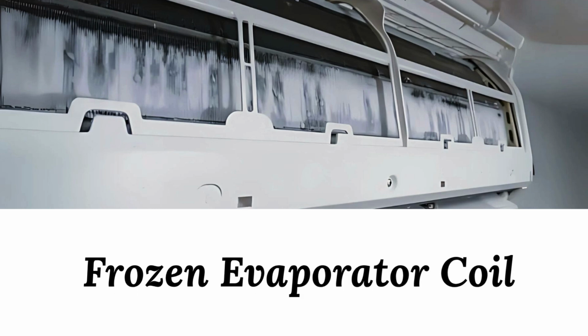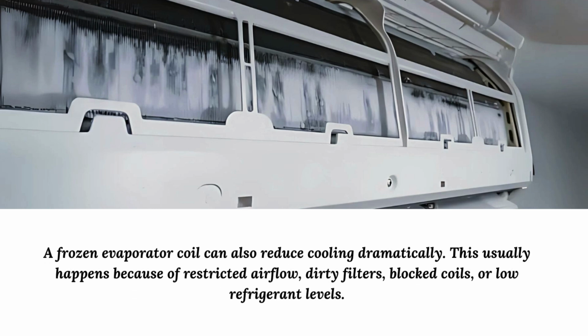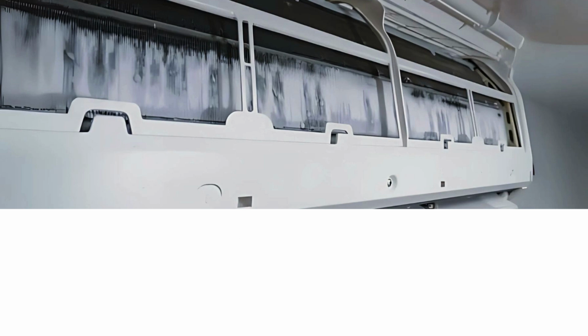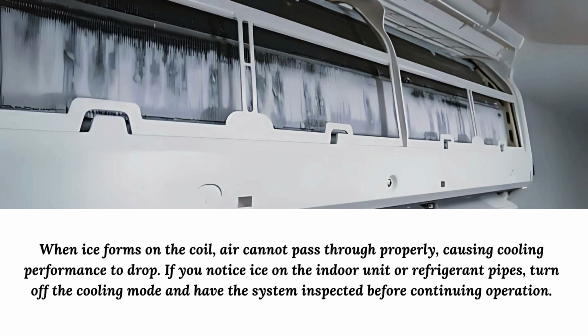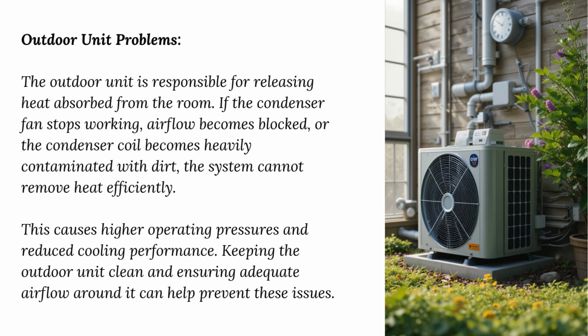Frozen evaporator coil. A frozen evaporator coil can also reduce cooling dramatically. This usually happens because of restricted airflow, dirty filters, blocked coils, or low refrigerant levels. When ice forms on the coil, air cannot pass through properly, causing cooling performance to drop. If you notice ice on the indoor unit or refrigerant pipes, turn off the cooling mode and have the system inspected before continuing operation.